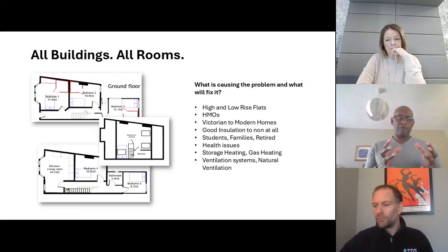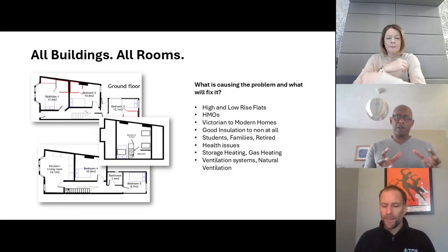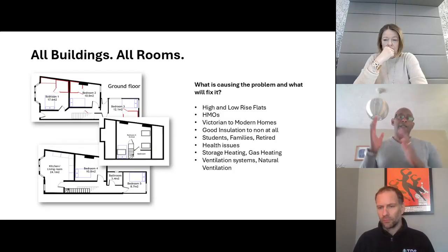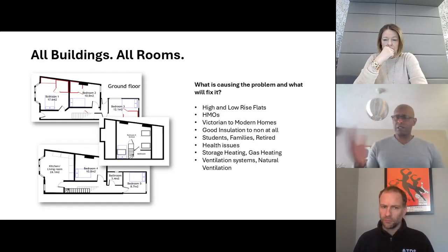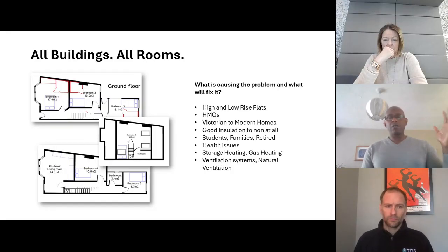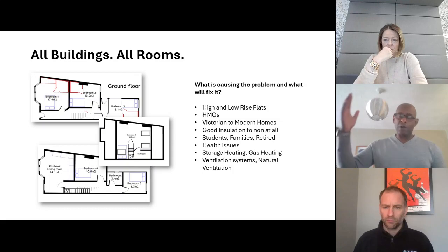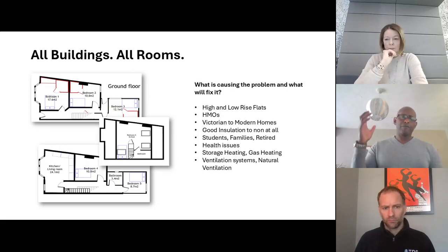One of them, working from home, ensuite shower. His habit was to go in the shower, open and close the door when he's having a shower, but then when he's finished, leave the door open. Now the wall was an external wall that didn't get much sun. It was going to be cold. We measured everything, and you could see in the data, as soon as that moisture came out of the shower, it just went straight to that wall. He was complaining that there was just water coming down, and it's just moldy. And because he's working at the desk there and trying to create a business from home, it was just horrible.